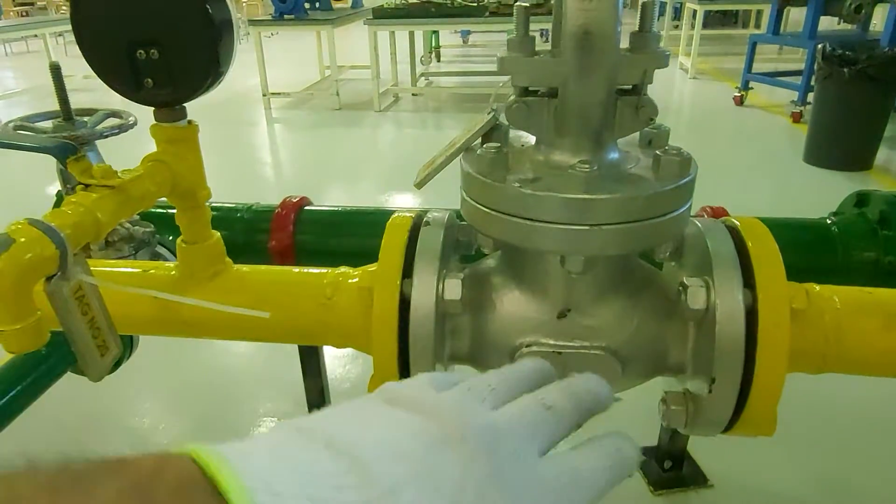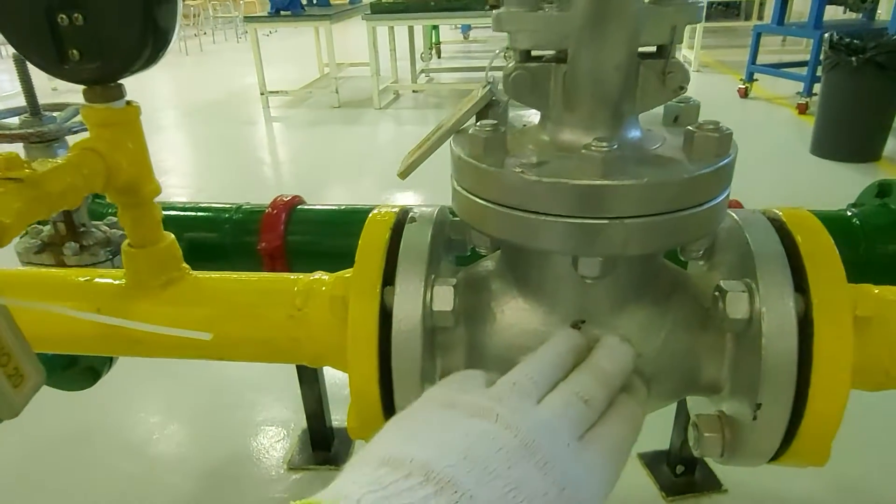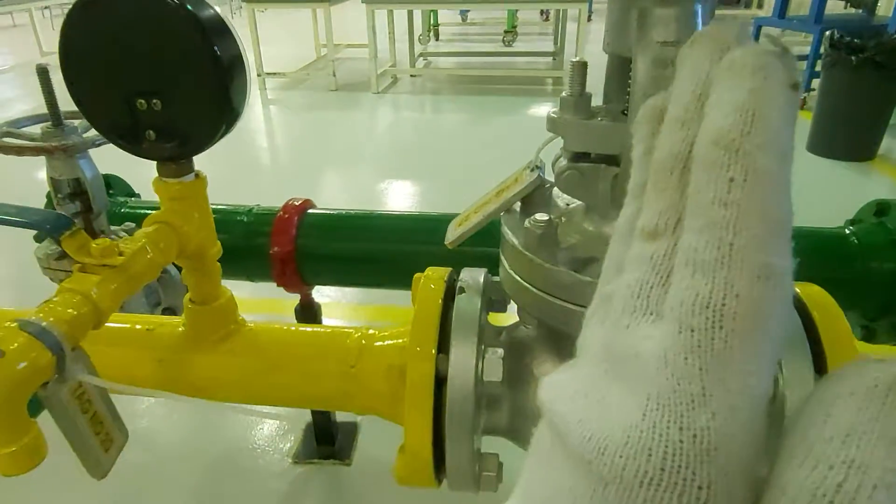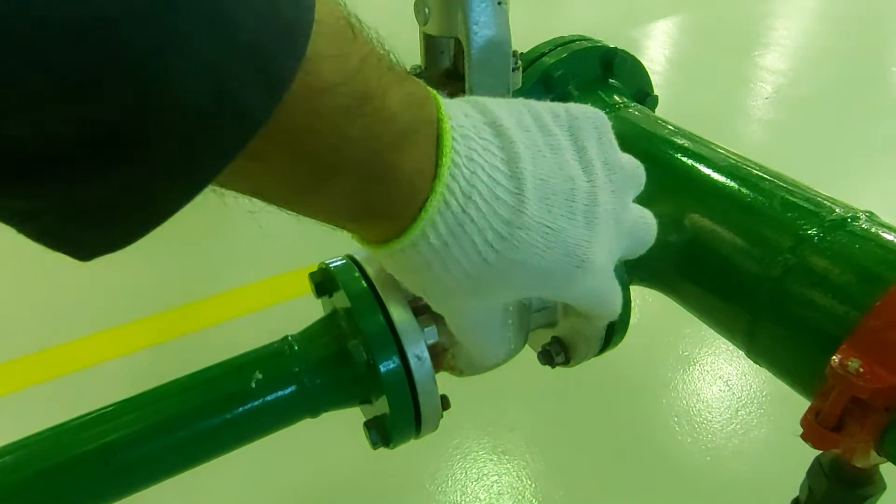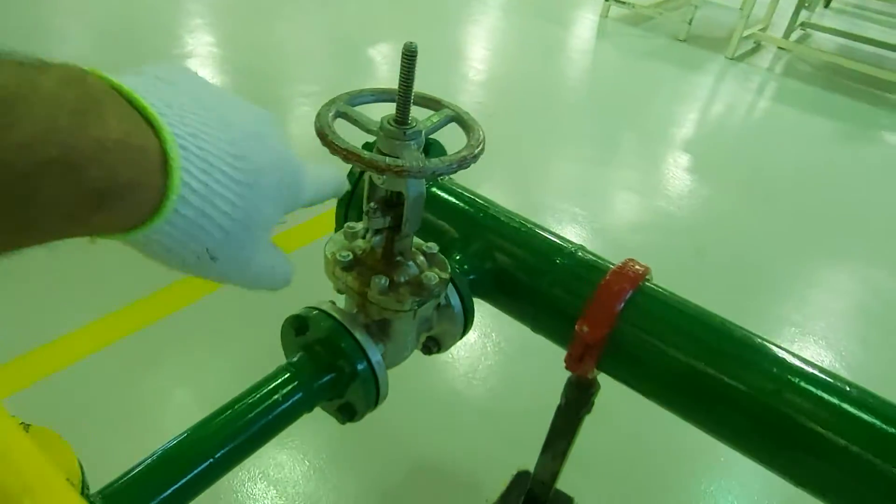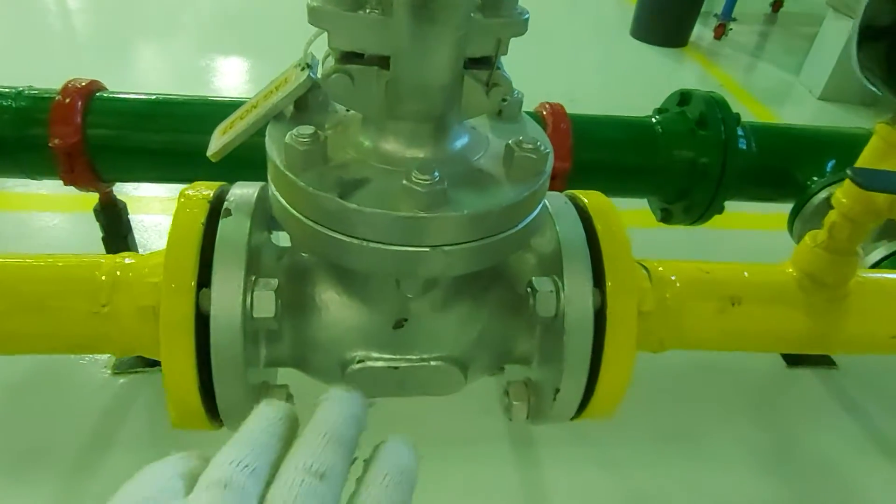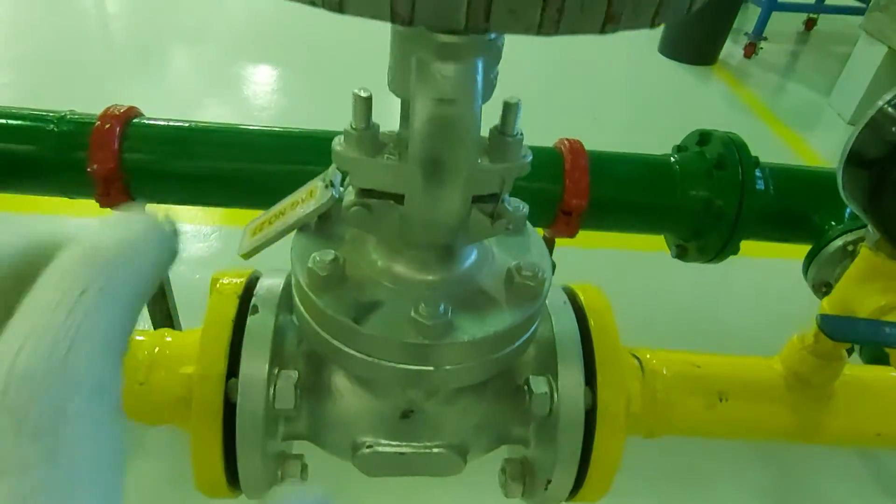The body is round, whereas if the disc is vertical, you will see the body is slim. That is a gate valve, and this one is a globe valve. Now, how does it open or close? Clockwise direction you close the valve, anti-clockwise direction you open the valve.